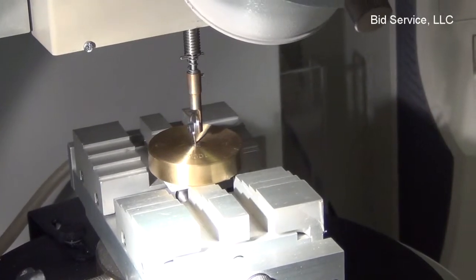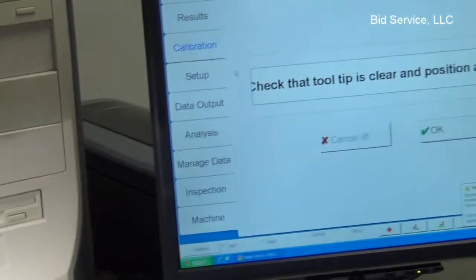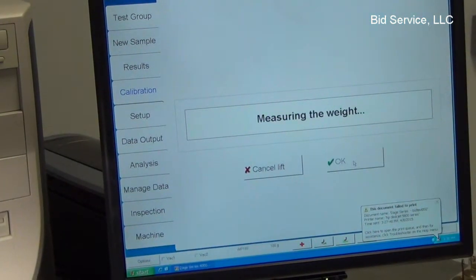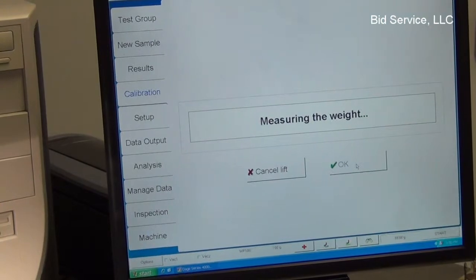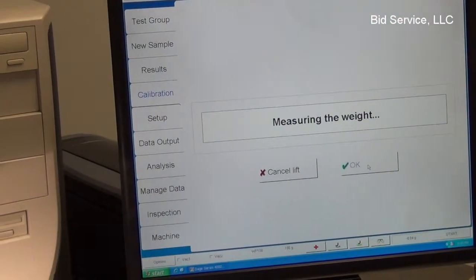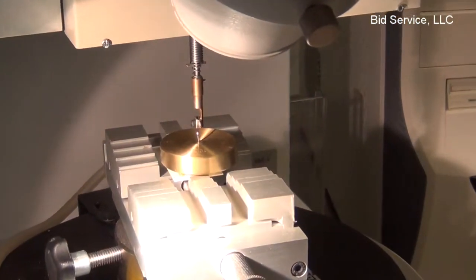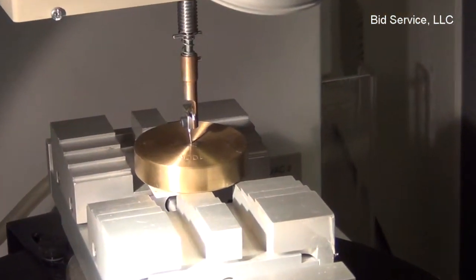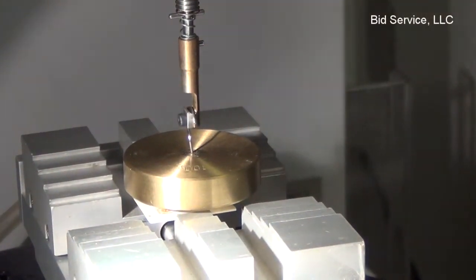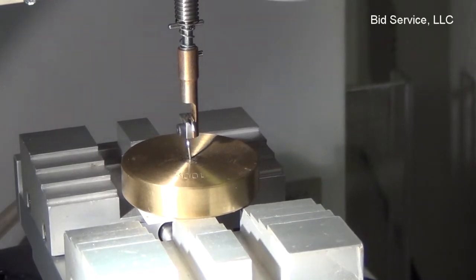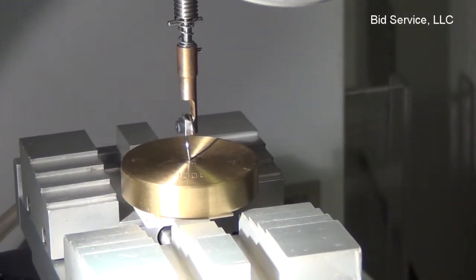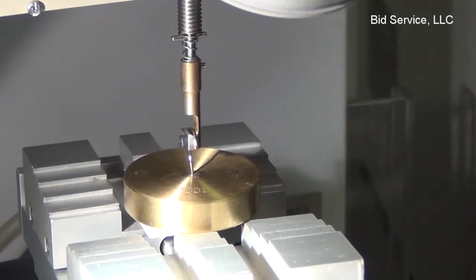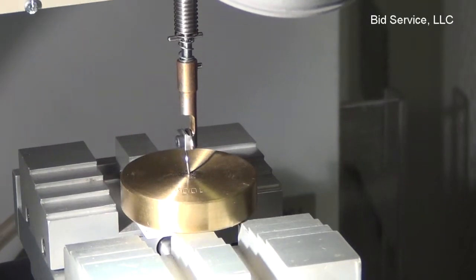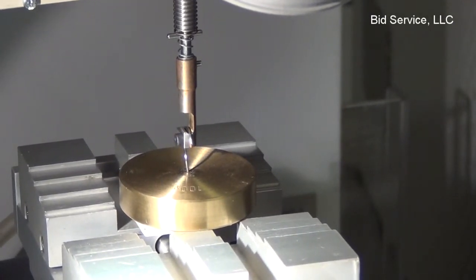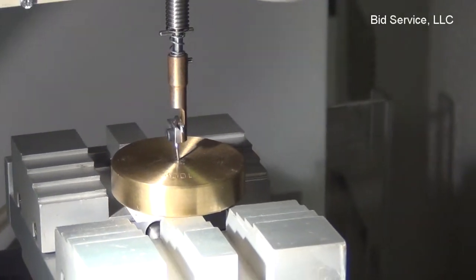Get into position. The tip is clear and the weight is in position, so I'm going to hit OK. Now if you look at the weight, it'll be lifted up a few times. And we get a calibration successful on the screen.